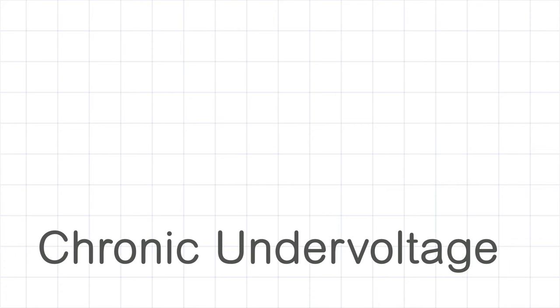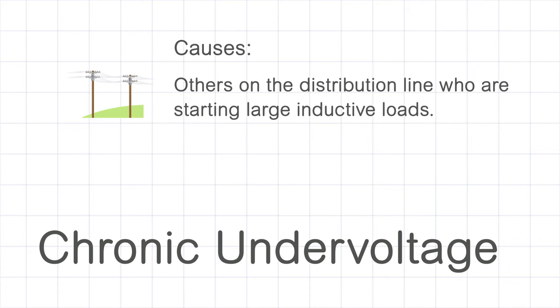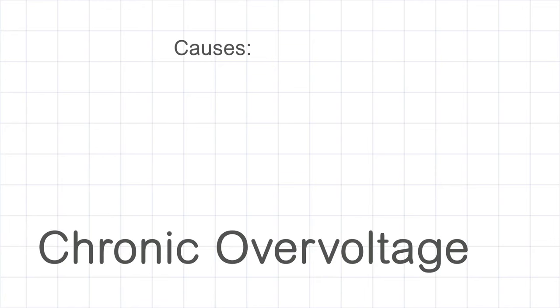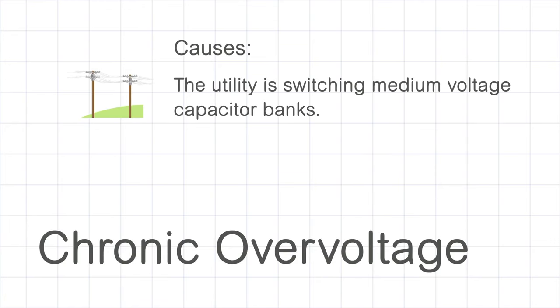Chronic undervoltage can happen because the consumer is at the end of a distribution line. A neighboring customer may be starting a large inductive load. A consumer may cause the sag with their own industrial process. Chronic overvoltage normally happens because the utility is switching capacitor banks on the medium voltage network.